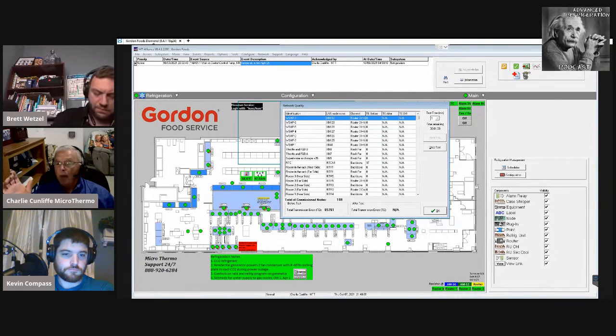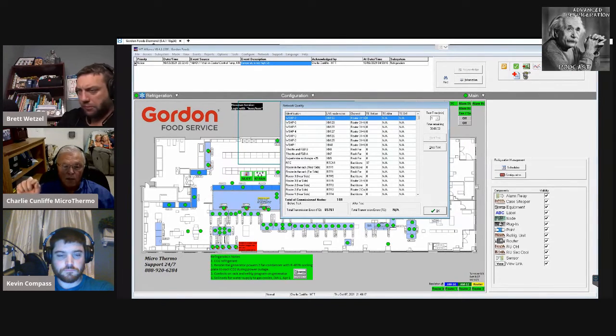If it is a combo board that has relays, there are momentary switches that you can toggle back and forth to physically hear the switch make or break on the control itself. And if you're close enough, you can hear that's a pilot relay. Then you can hear either a big relay make or break, or a fan come on or off, or a compressor come on and off based on the action of the momentary switch. So I would make sure that I have power.